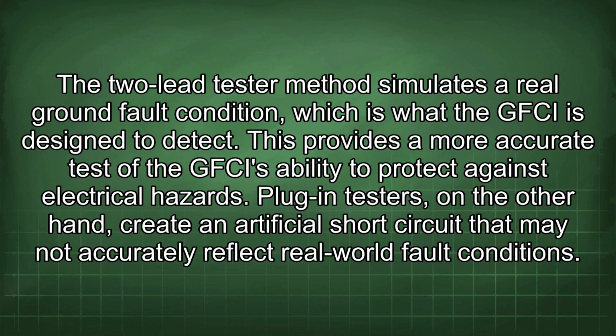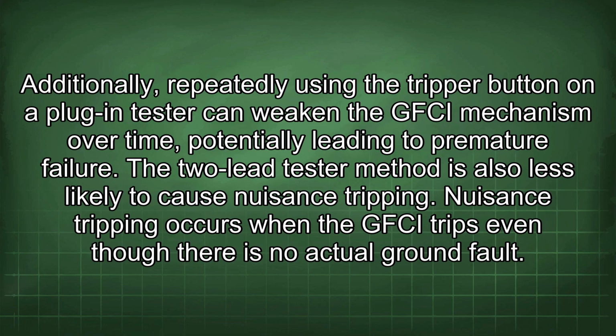The 2-lead tester method simulates a real ground fault condition, which is what the GFCI is designed to detect. This provides a more accurate test of the GFCI's ability to protect against electrical hazards. Plug-in testers, on the other hand, create an artificial short circuit that may not accurately reflect real-world fault conditions. Additionally, repeatedly using the tripper button on a plug-in tester can weaken the GFCI mechanism over time, potentially leading to premature failure. The 2-lead tester method is also less likely to cause nuisance tripping.